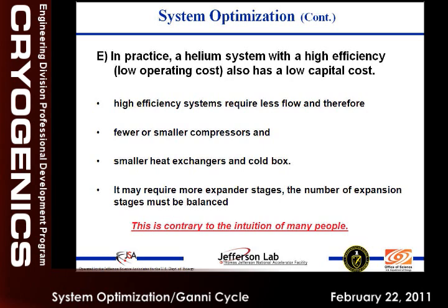And that's where I started working when I became a user from the vendor. I spent my initial time working on that, on where this trade-off is, and found the most efficient system is, why I say so, the more efficient the system, you need less compressor, you need smaller heat exchangers, smaller buildings. If you trade everything into efficiency, you already paid for the increased number of Carnot steps by reduced compressors and heat exchangers. So there is an optimum in terms of how far you can push this efficiency.